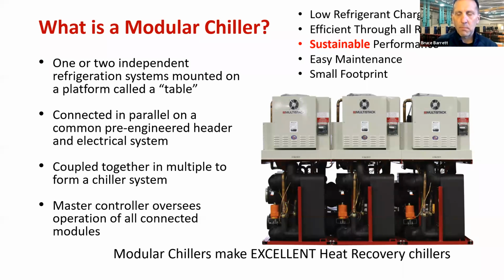Do have to talk a minute about modular chillers and why they offer a differentiator to a single machine, a screw or a centrifugal that has a single bundle. We've got multiple independent refrigerant circuits piped in parallel. We've got a common master controller controlling each one of those. Each one of those modules can be isolated electrically and hydronically.